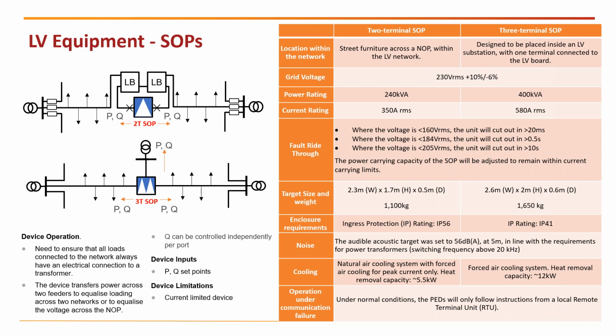In particular, from a thermal performance perspective, silicon carbide will give us the opportunity to provide more power without incurring thermal issues. At the same time, it allows switching frequencies that are much higher than conventional material. We are talking about a 20 kilohertz switching frequency, which will enable us as a DNO to install these devices in places where it's most convenient from an electrical perspective, without incurring noise which can disturb our customers.